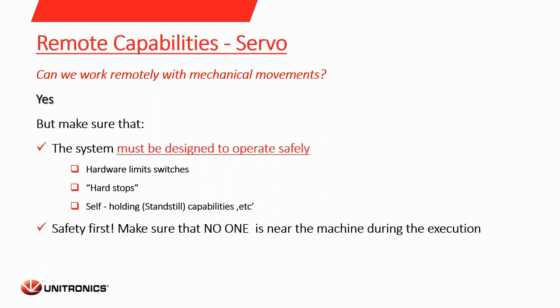The basics would be having hardware limit switches. Maybe even designing hard stops and bumpers to avoid damaging your mechanics if it reaches the end of travel. Your system should also have self-holding capabilities — it can be a holding brake, or maybe working with a ball screw and a pitch that is relatively small. The system should be able to hold itself in position when not powered or if a disconnection occurs. Please make sure no one is near the machine during execution so no one gets injured.